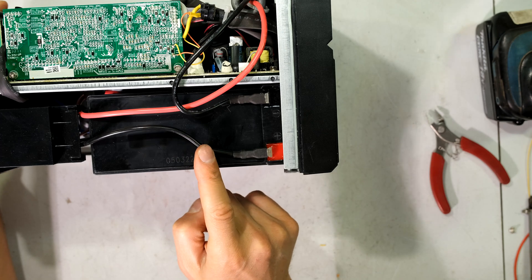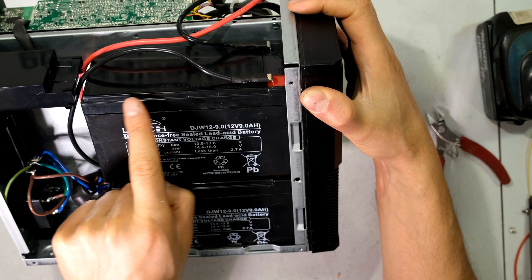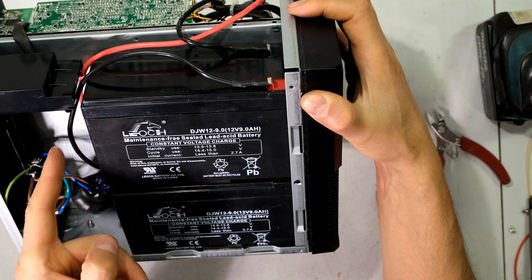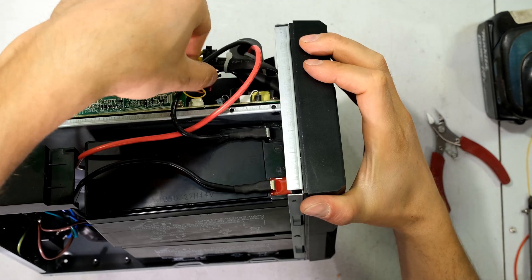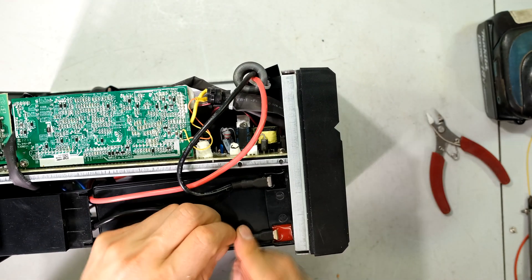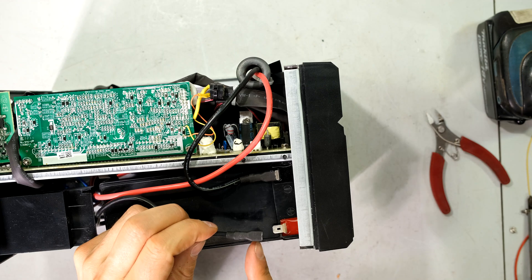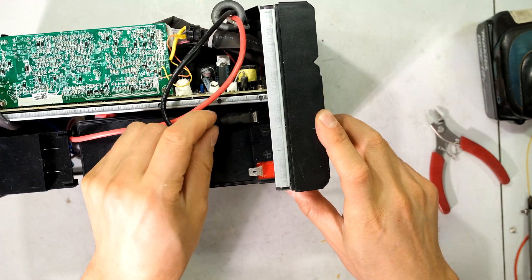Now I have access to my two batteries. I start by removing the two connectors on the top battery. These batteries are connected in series, so it's very important to get the wiring layout correct. This wire here is black because it is coming from the black underneath — it goes negative to positive on the top battery, and then the negative of the top battery goes to the MOSFETs installed underneath. This wire going to the electric circuits on the side is connected here. You might need considerable force to remove it — wiggle it a little and there it comes off.